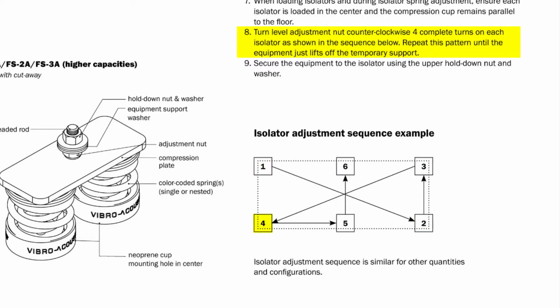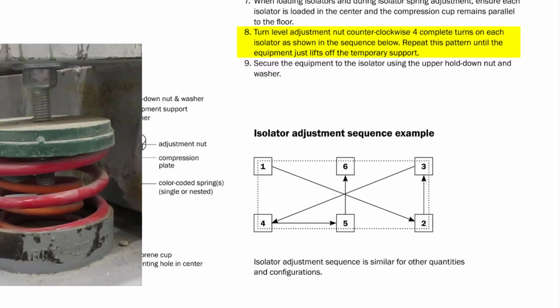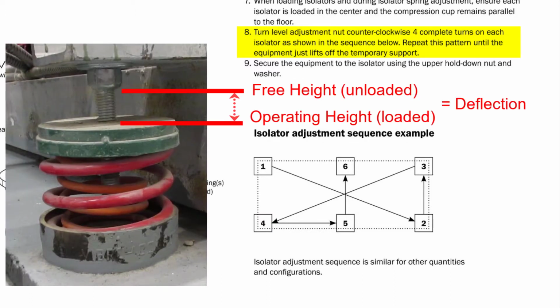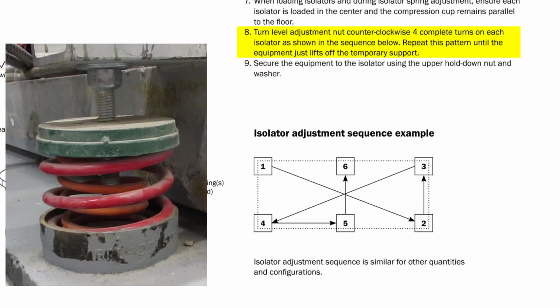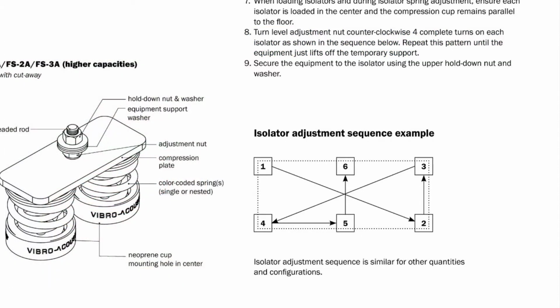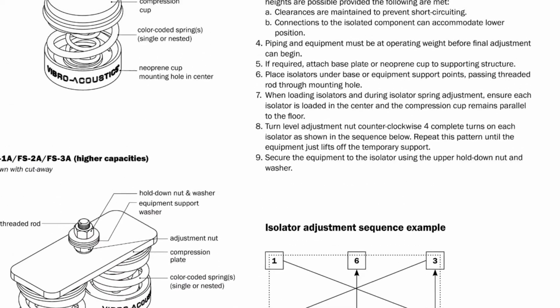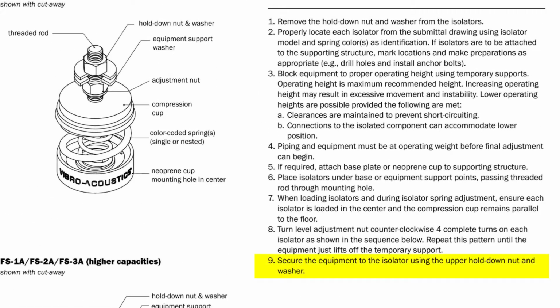We can see evidence that these instructions were followed on the job site by looking at the amount of deflection on each isolator. If the installer follows this adjustment method, then the isolators should be very close to their design deflection. However, if the installer tried to adjust one isolator too much before adjusting another, then there will be greater variation and possibly over-compressed springs, a common mistake with spring isolators. And finally, as mentioned already, the hold-down nut should be tightened.